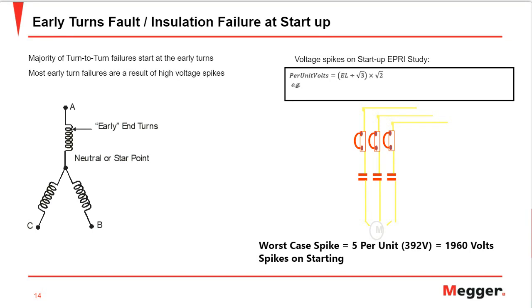The rise time of these spikes is around 0.2 to 0.5 microseconds, a very short period of time. But these spikes can go up to 5 times the per unit value of that motor. In this case, let's consider 480 volts. The per unit value is what we use to have every parameter on the same page. So 5 times the per unit value, we get around 1960 volts, which is a lot for a 480 volt motor. But this is the voltage which a motor experiences every time it is started.